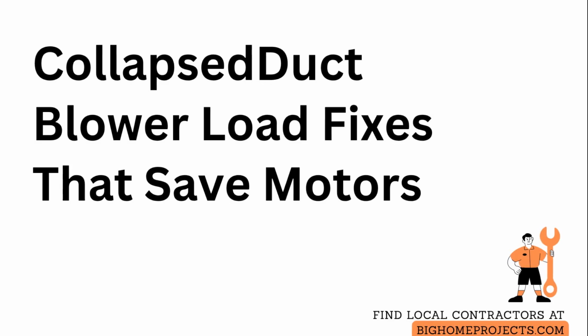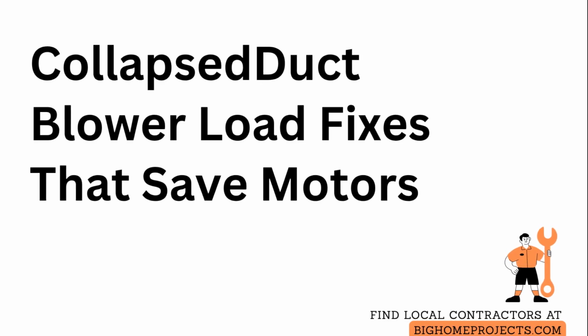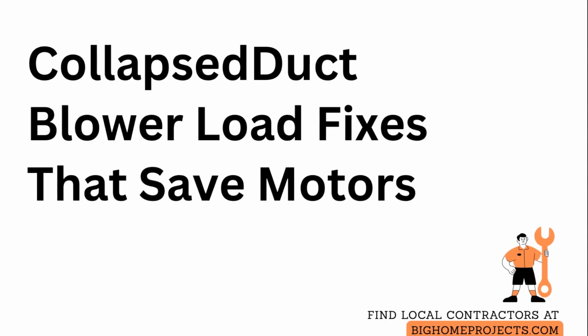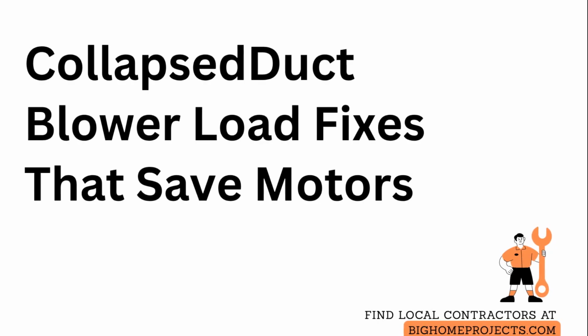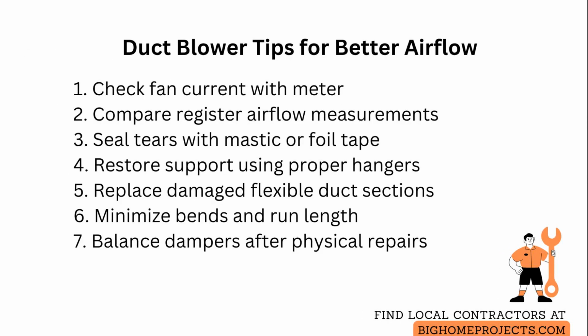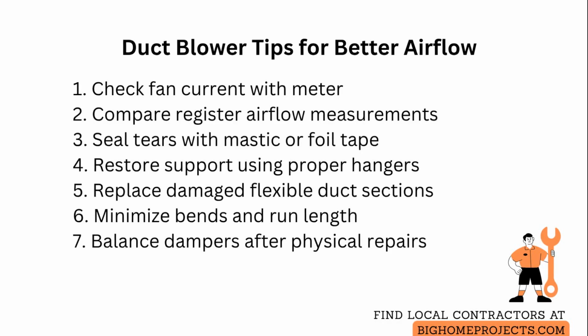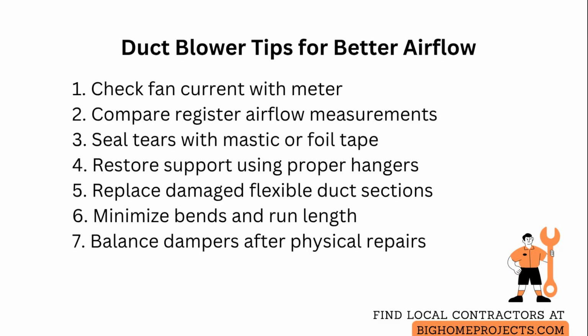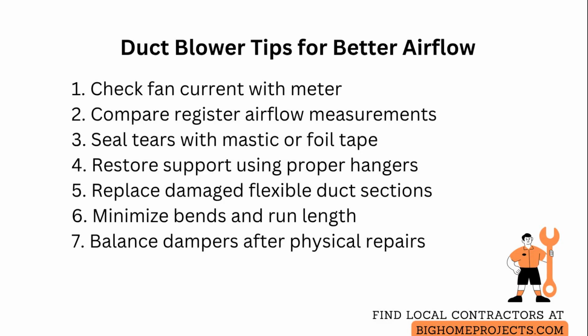A collapsed or open duct changes blower operation by altering airflow and motor load, which can cause poor comfort and premature equipment wear. When a duct is collapsed, the blower sees increased static pressure that forces it to work harder to push air through restricted pathways, raising motor current and reducing delivered airflow at registers.